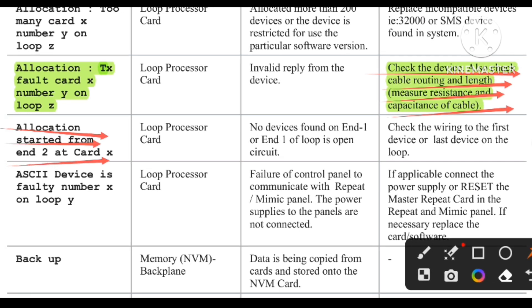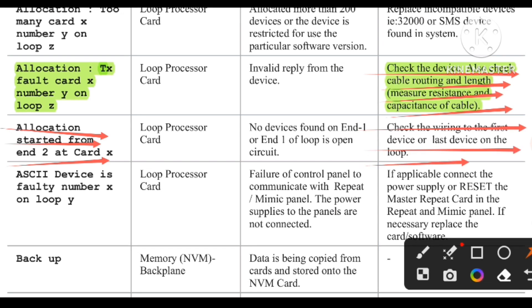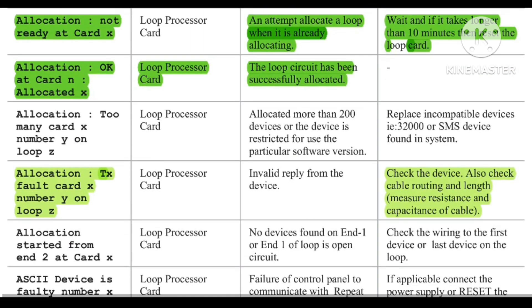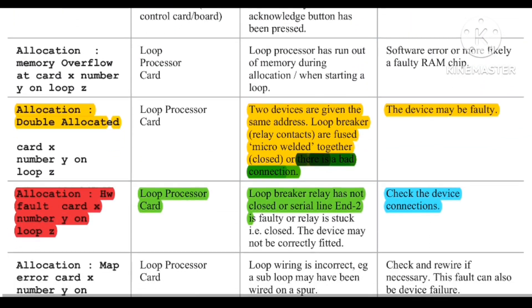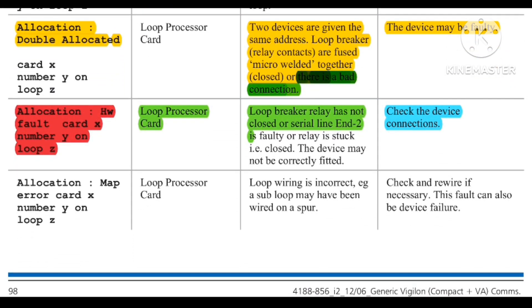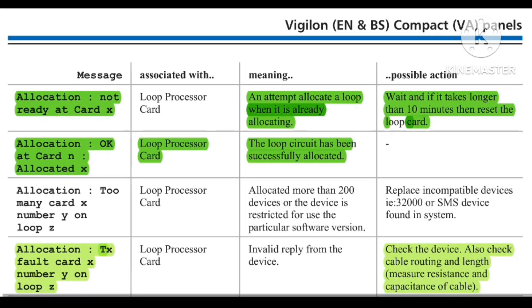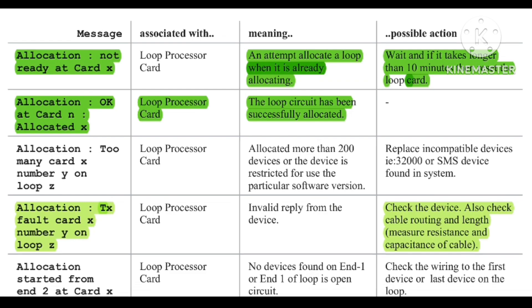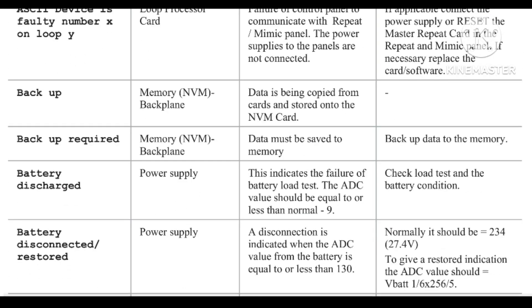If 'Allocation started from end' appears, check the wiring to the first or last device. To summarize, the allocation faults covered are: allocation memory overflow, allocation double allocated, allocation HW fault, allocation map error, allocation not ready at card X, and allocation TX fault — all very common faults in the Gent Vigilon panel.